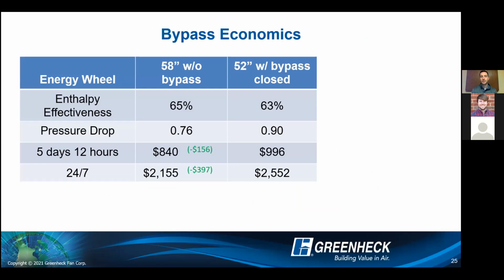Looking at the economics of these two different wheels, without bypass you see an enthalpy effectiveness of about 65%. Compared to the 52-inch wheel, even if the bypass is closed and all of that air is going through the energy recovery wheel, because it's a smaller wheel, the enthalpy effectiveness actually goes down a little bit. So it's 63%, not a huge reduction, but you would still potentially be able to downsize your cooling and heating downstream, or you would save energy on the capacities required when using energy recovery. Another thing to look at is pressure drop. A lot of the conversation around wheel bypass is that during economizer mode you get a reduction in pressure drop during those times. But with the larger wheel, you actually get a lower pressure drop during normal operation because your wheel is larger. It's about 0.76 in this case versus 0.9 with that 52-inch wheel with bypass closed.